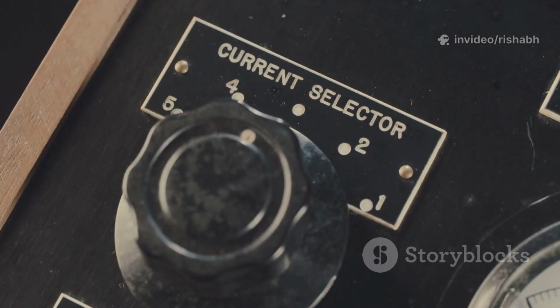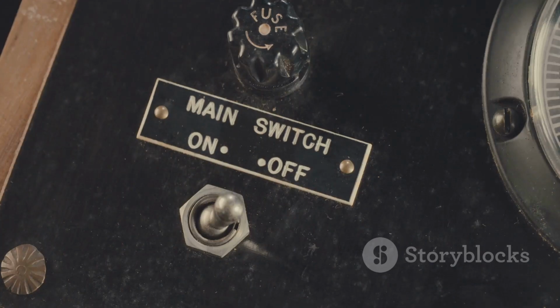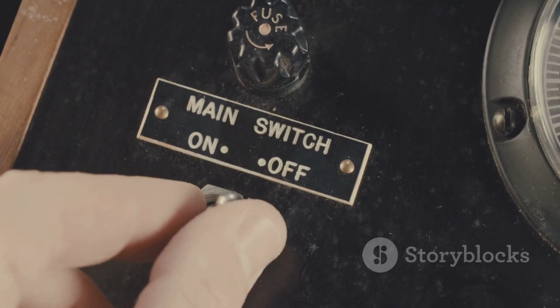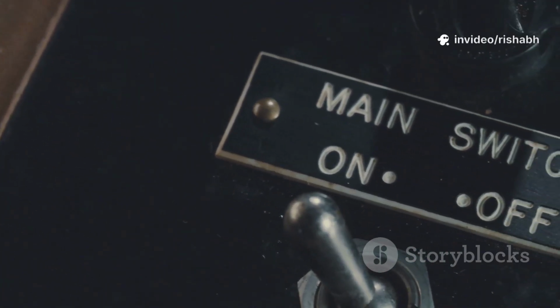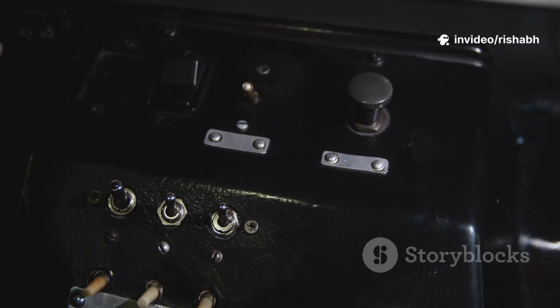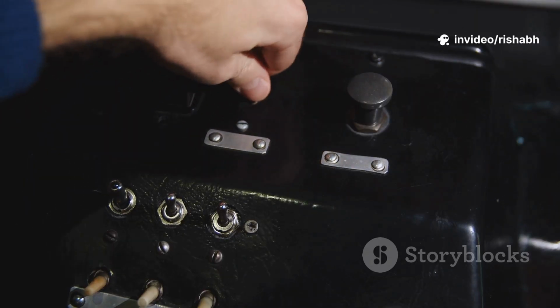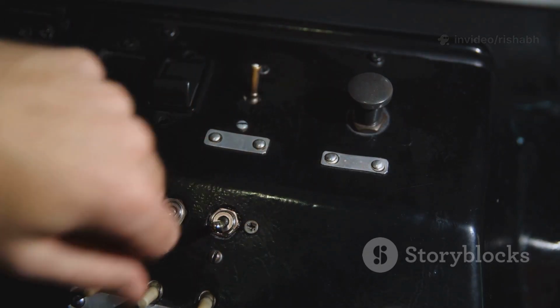It pre-selects the next physical tap on the winding that we want to move to. It does not carry or break any current itself. The real magic happens in the diverter switch. This is a high-speed, spring-loaded device that performs the actual current switching operation.